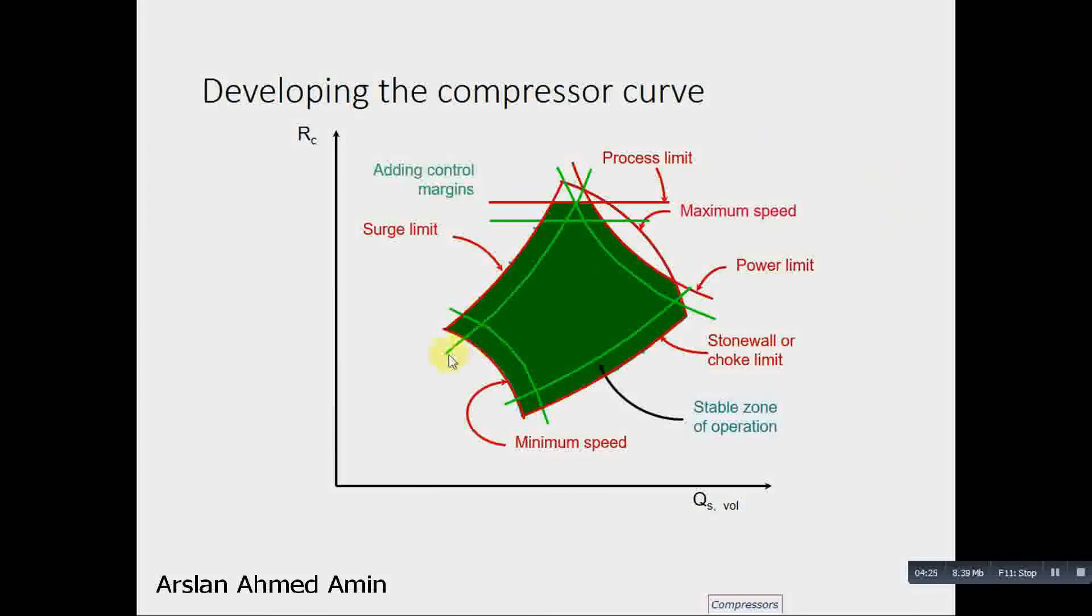We further add margins for our stability of the compressors. We will see that we have added margins. We can say that the margin is 10%. Usually a 10% standard margin is used. So we want the compressor to operate in this region. This is a further safer region.